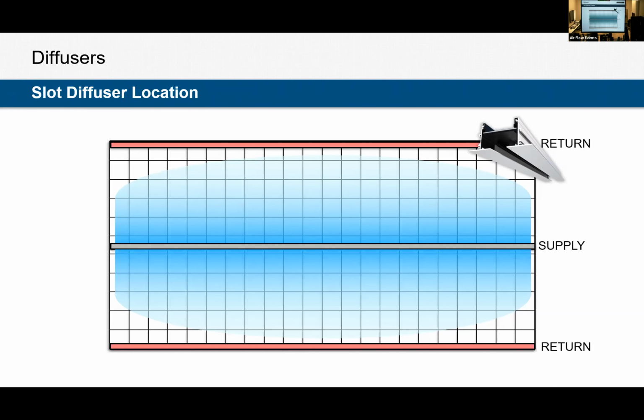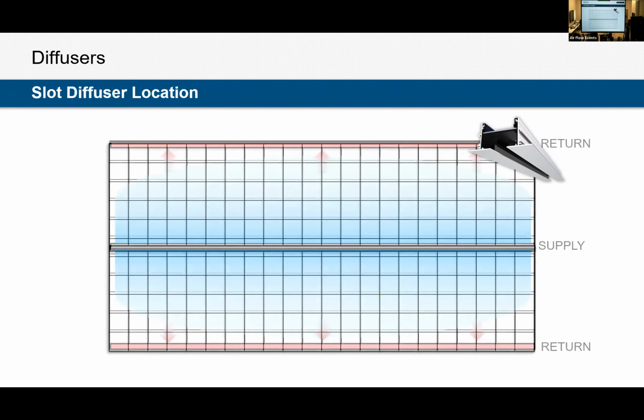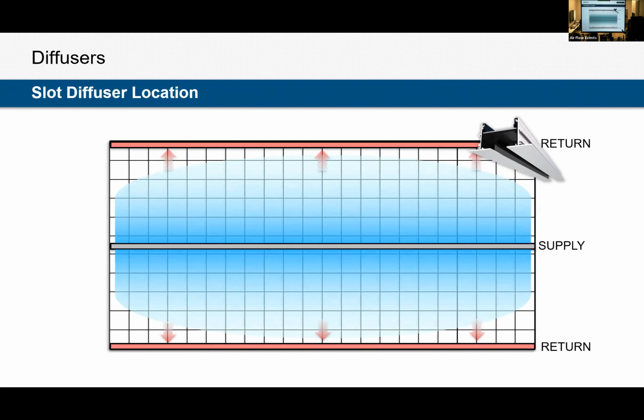So yes, this configuration here, I should have put some more animations, maybe that would have given you guys the answer. This configuration here is what we call short circuiting. That is, you travel right across the ceiling and get sucked up into the return, not allowing for any mixing in the space. So ideally, let me ask you guys, where should we put the returns then?